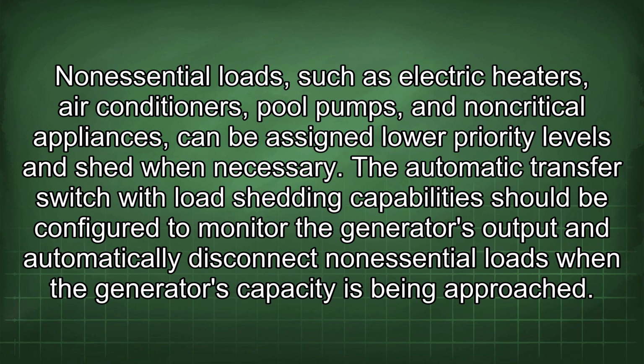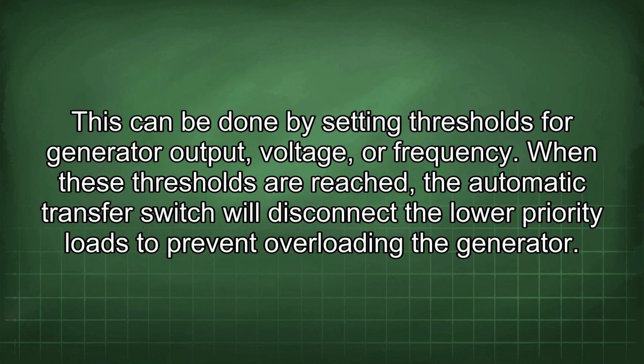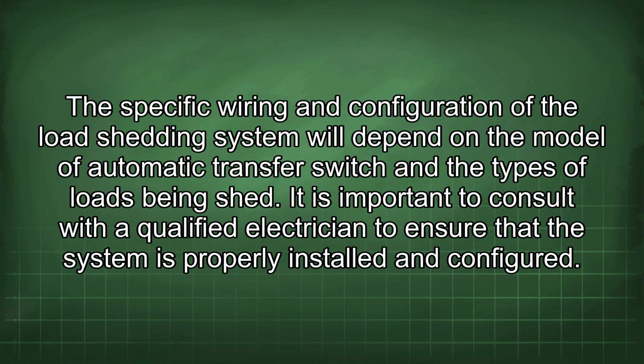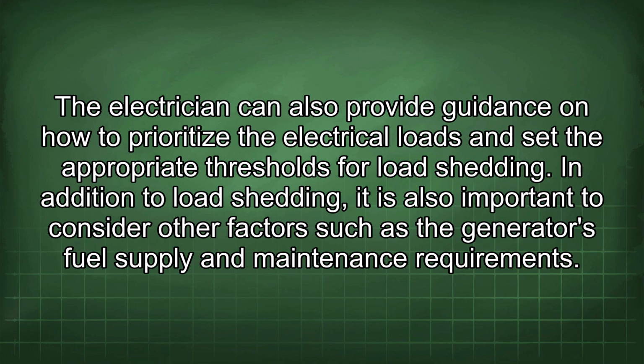and shed when necessary. The automatic transfer switch with load shedding capabilities should be configured to monitor the generator's output and automatically disconnect non-essential loads when the generator's capacity is being approached. This can be done by setting thresholds for generator output, voltage, or frequency. When these thresholds are reached, the automatic transfer switch will disconnect the lower priority loads to prevent overloading the generator. The specific wiring and configuration of the load shedding system will depend on the model of automatic transfer switch and the types of loads being shed. It is important to consult with a qualified electrician to ensure that the system is properly installed and configured.